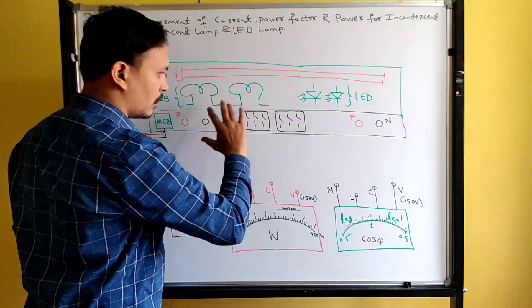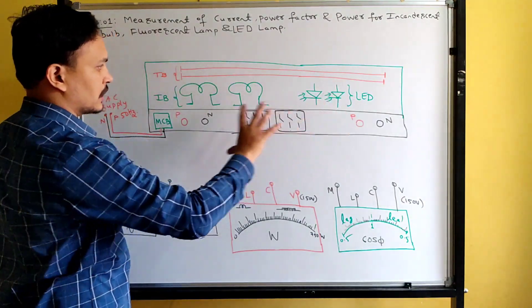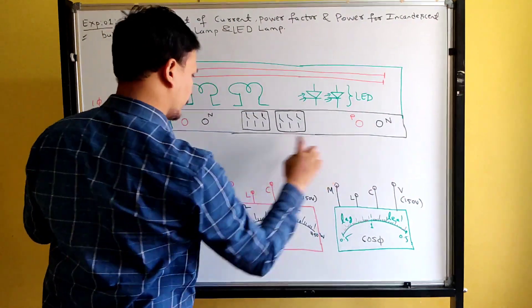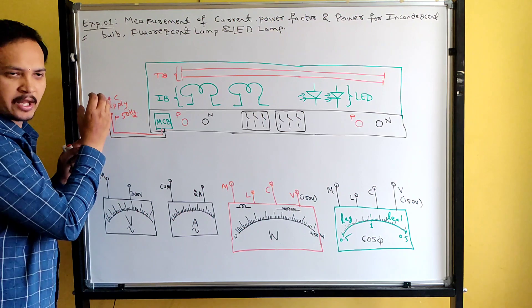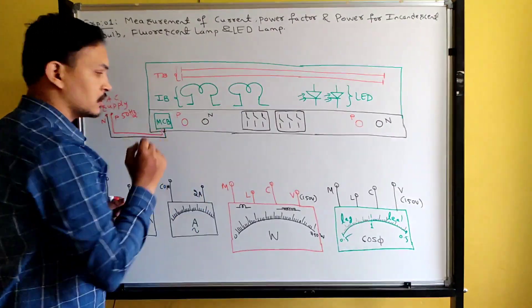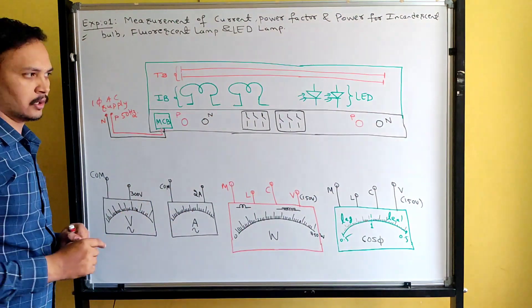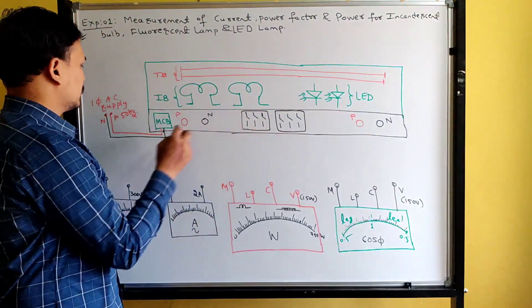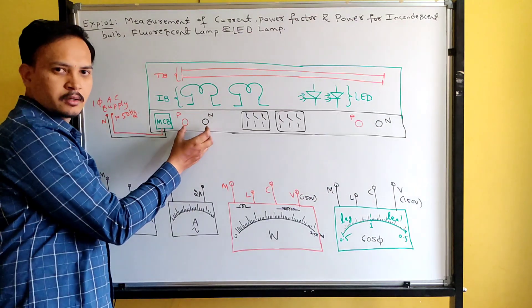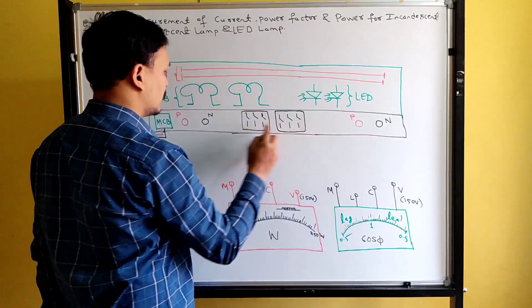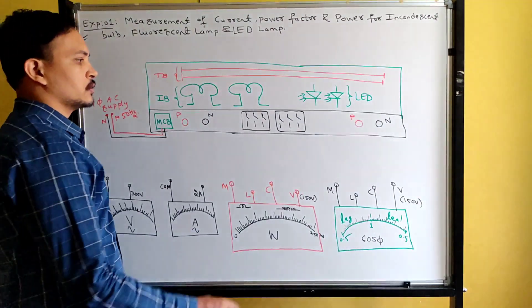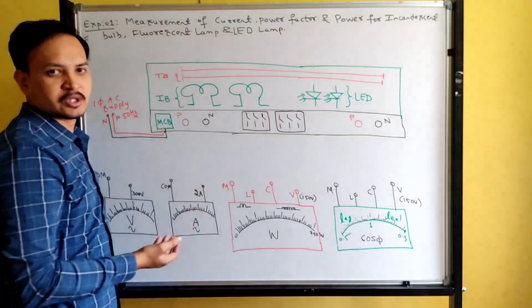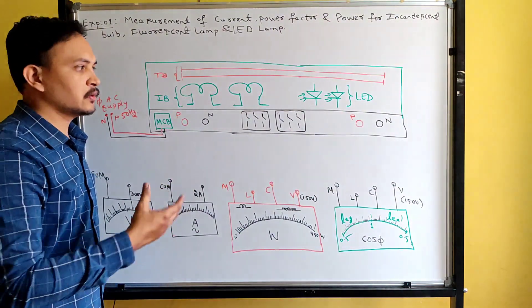Totally six lamps, and all the lamps are connected in parallel. Now, give supply to this MCB — this entire panel board. This entire lamp load bank is connected to the single phase AC supply. These two are supply terminals and these two are load terminals. If I switch on the MCB, this supply will come and be available at this point. But if you connect phase to phase and neutral to neutral directly, you cannot measure power consumed, current carried by the load, or power factor of the load.